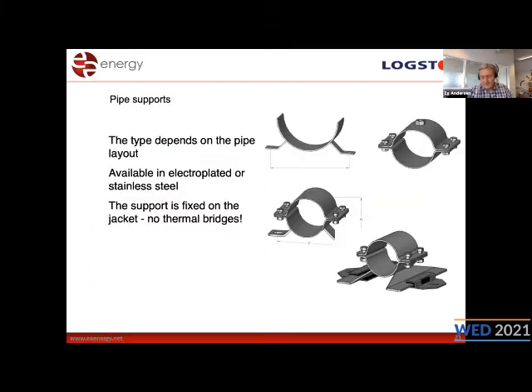And then another advantage using the pre-insulated pipe system is that you have the pipe supports outside on the jacket. You put it around the jacket. Well, it means that you don't put a support in touch with the media pipe, because then you have an energy bridge. You have typically a heat bridge that costs a lot of energy, which I will get back to later in a calculation system.